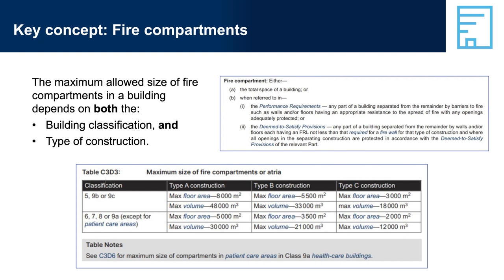For example, a building may only be required to be built using Type C construction. If this would result in fire compartments that are too small to be practical for the purpose of the building, then the building designer could use a more fire-resistant type of construction — Type B or Type A. This would then allow design and building of larger spaces while still complying with performance requirements. There are special rules for large, isolated buildings of Class 5 to 9 under C3D4.